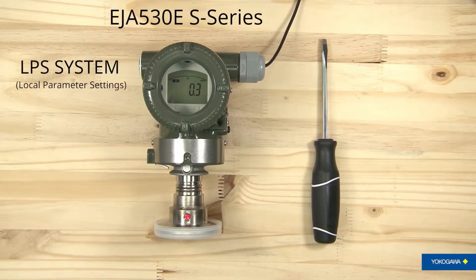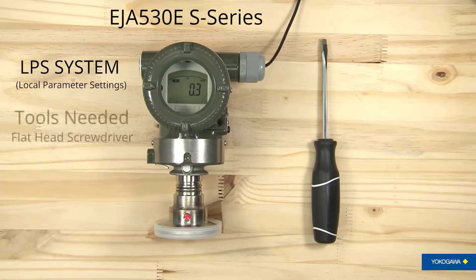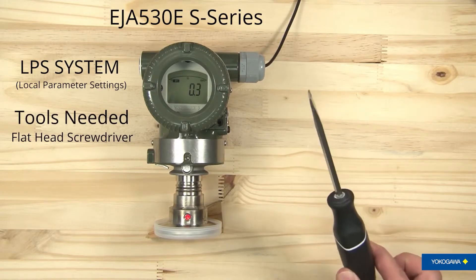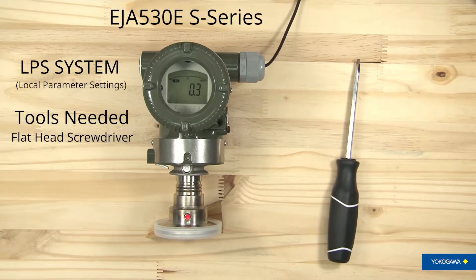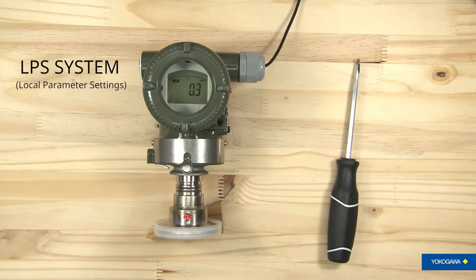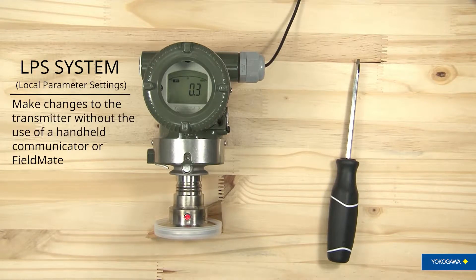Today we're going to look at the Yokogawa LPS system on our pressure transmitters. What you'll need for this is a flat head screwdriver. We're going to be using an S Series EJA530E and go through and show you how to use the LPS. The LPS allows you to make changes to the transmitter without actually having a handheld communicator or FieldMate.